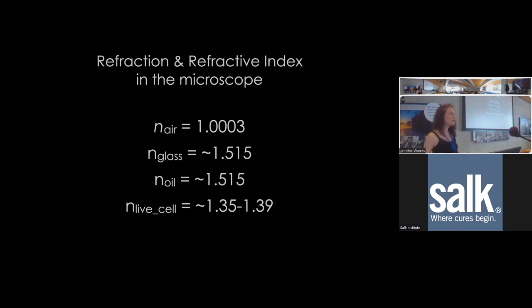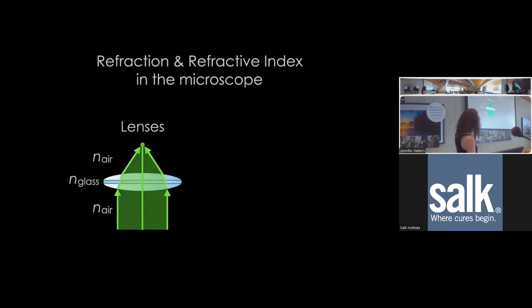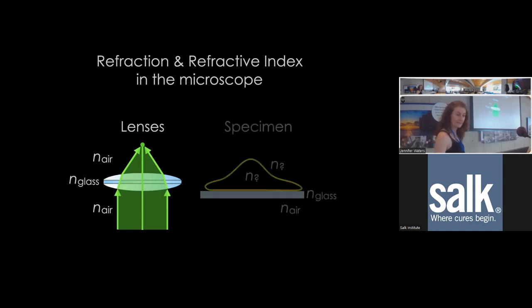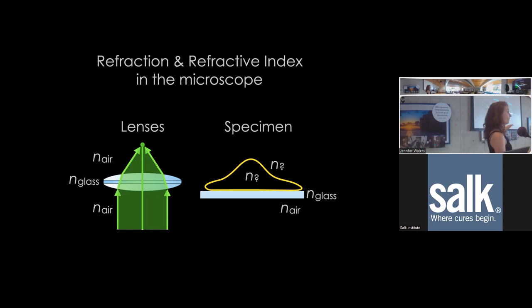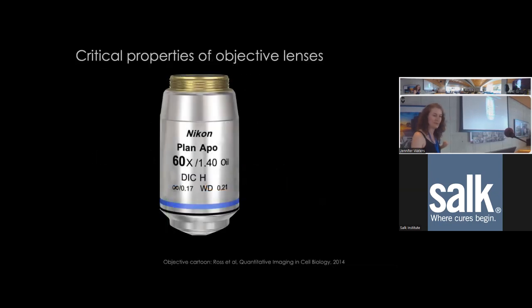Lenses focus light based on refraction: light travels through air, hits glass, refracts, hits the next glass surface, enters air, and refracts again to focus to a point. Your specimen sits on glass, which has a different refractive index than air, and your sample also has some refractive index—different from the glass or immersion media, especially for live biological samples. The objective lens has many important markings. The correction phrase (e.g., Plan Apo) indicates how well the lens has been corrected for aberrations. After the magnification is the numerical aperture, a critical number in the resolution equation.